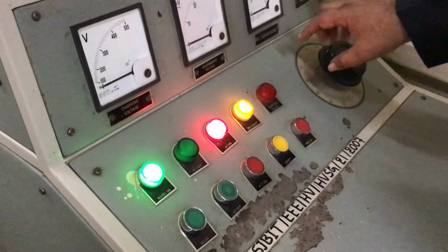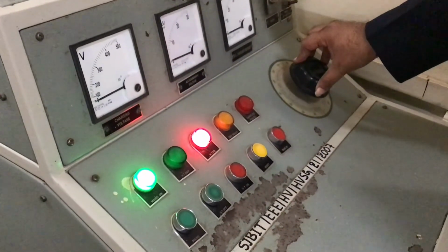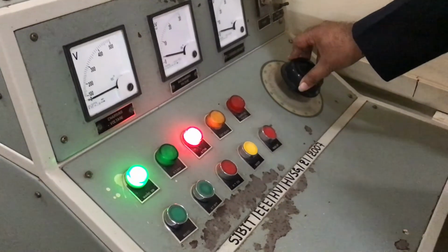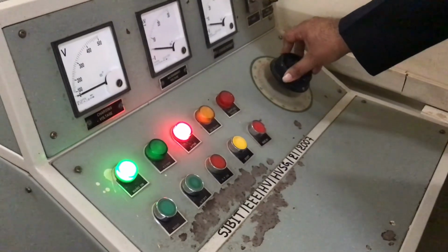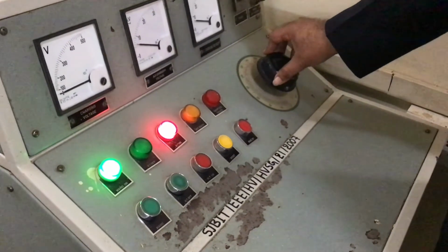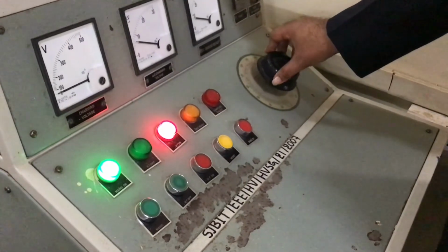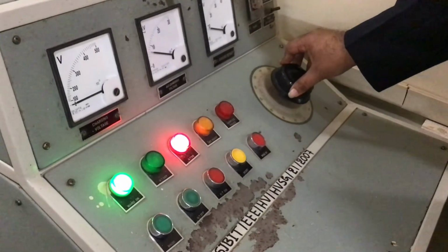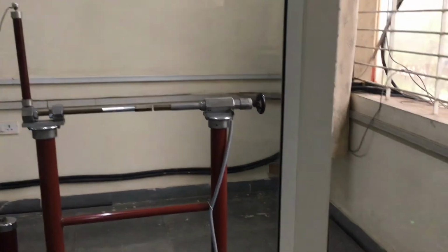Now I will slightly increase the voltage. You can see it here — it has crossed 5 kV, then further to 7 kV, with a hissing noise. Around 8 kV it tripped.